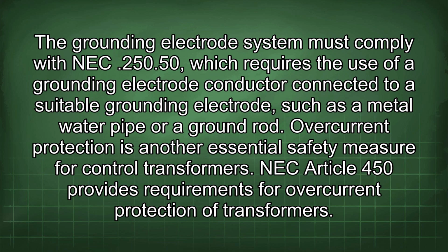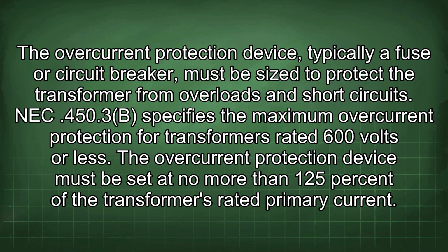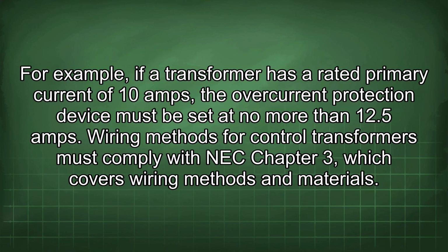Overcurrent protection is another essential safety measure for control transformers. NEC Article 450 provides requirements for overcurrent protection of transformers. The overcurrent protection device, typically a fuse or circuit breaker, must be sized to protect the transformer from overloads and short circuits. NEC 450.3(B) specifies the maximum overcurrent protection for transformers rated 600 volts or less. The overcurrent protection device must be set at no more than 125% of the transformer's rated primary current. For example, if a transformer has a rated primary current of 10 amps, the overcurrent protection device must be set at no more than 12.5 amps.